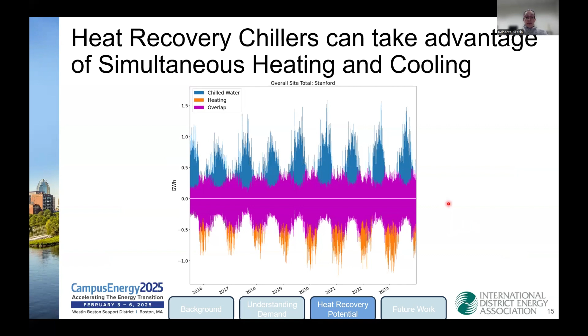Now, you may have attended some IDEA presentations in the past, like I did last year, where there were several stories of people saying the heat recovery chillers did not work on my campus. Part of the reason that I believe they have not been as successful at different campuses possibly comes from the fact that a lot of times these heat recovery chillers were implemented on the building scale instead of at the campus scale. Here we can see that there is quite a bit of overlap between heating and cooling demands at the campus scale. By going bigger and trying to meet these demands and take advantage of the simultaneous heating and cooling at the campus level, I think there's a much larger opportunity to implement heat recovery chillers than just at the building level.